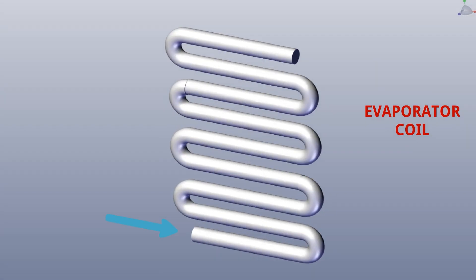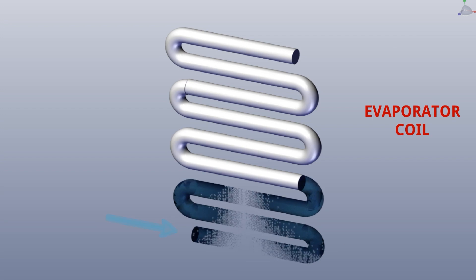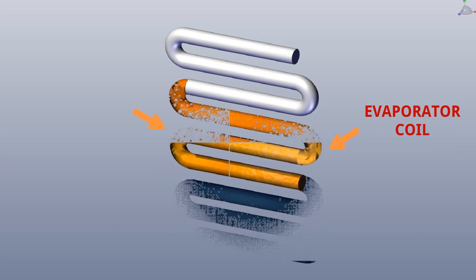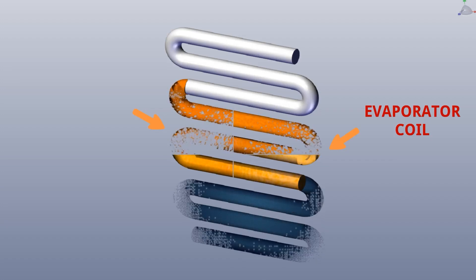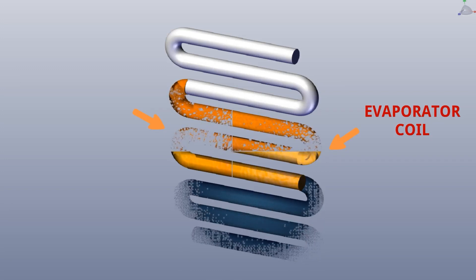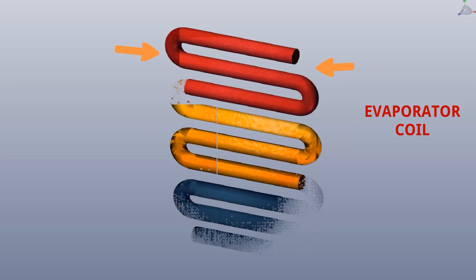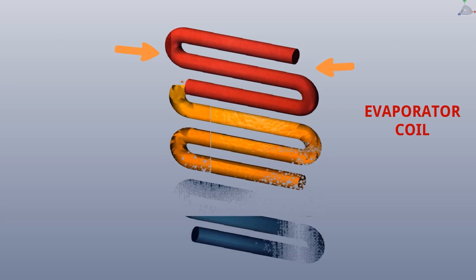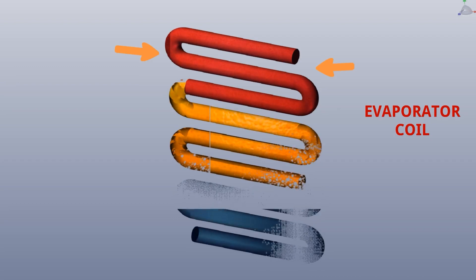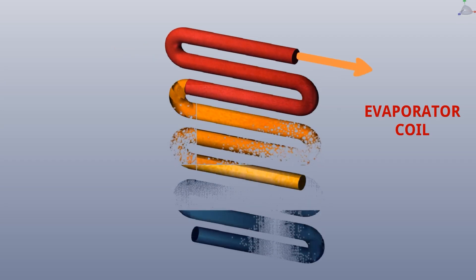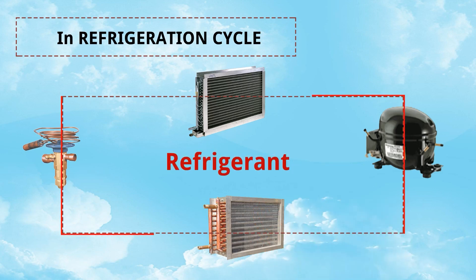This is the evaporator coil. Cold refrigerant enters the evaporator coil and takes heat from the surrounding air, becoming heated and forming a liquid-plus-vapor mixture. The liquid refrigerant changes into liquid plus vapor as temperature increases. Then it takes more heat and finally becomes refrigerant vapor — first saturated vapor, and then slightly superheated vapor — and it leaves from the evaporator coil.